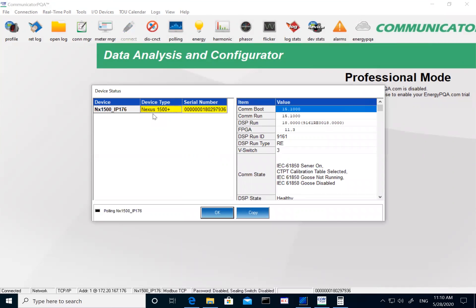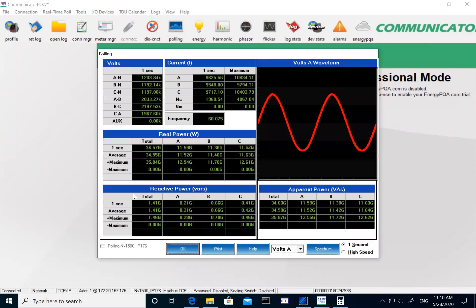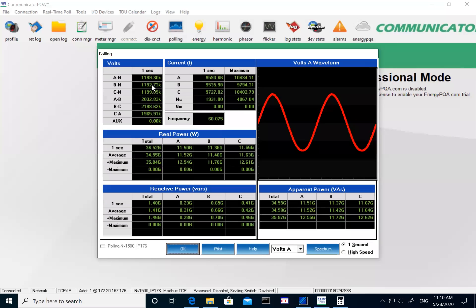It connects to the meter and brings up the meter information — the serial number and type. You can see I'm connected to the Nexus 1500 Plus. I'll click OK. On the top you have different icons; I can look at real-time readings showing voltage, current, and power readings. This is an important screen when you want to match the readings you're getting on the DNP versus what's on the meter side.